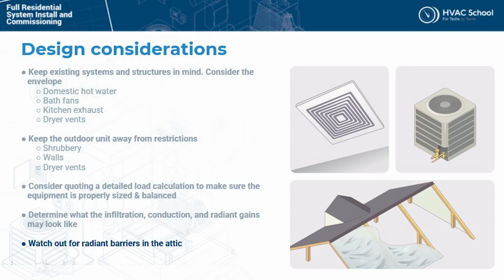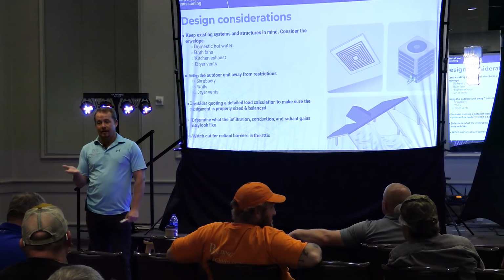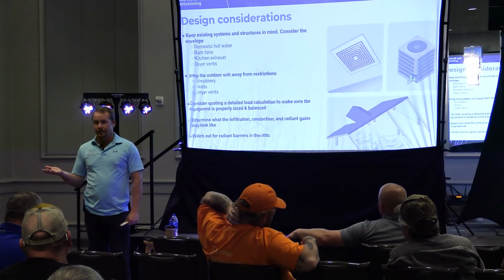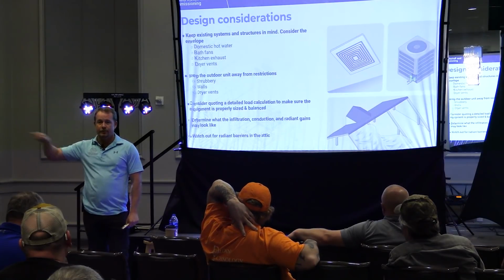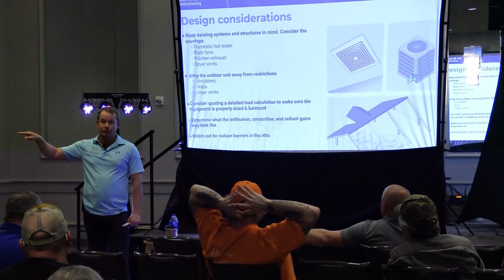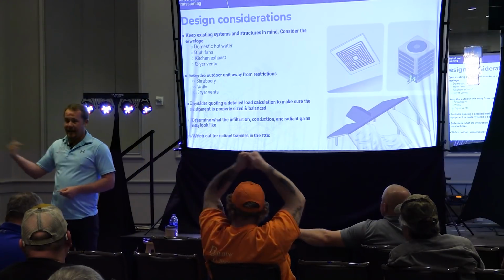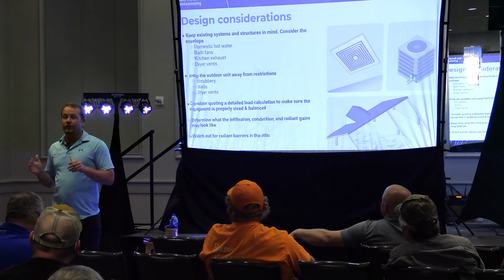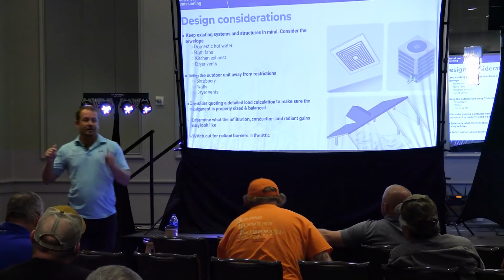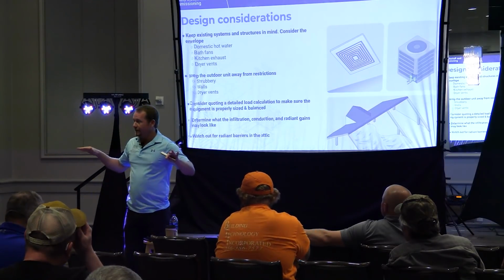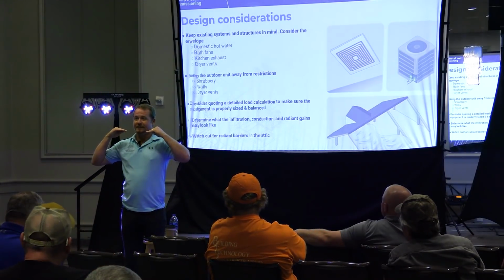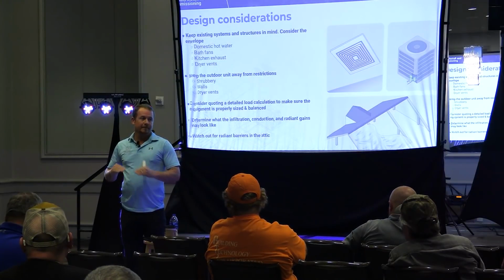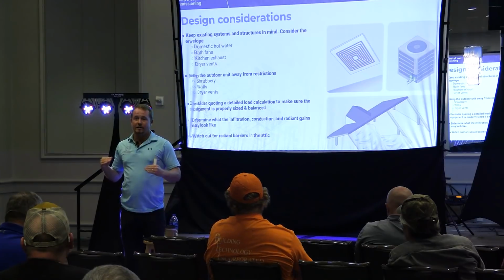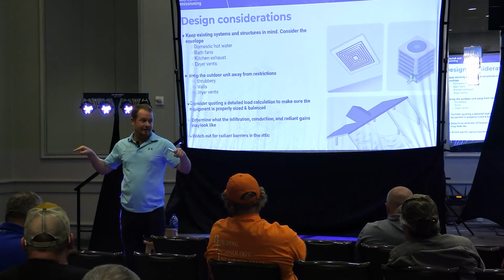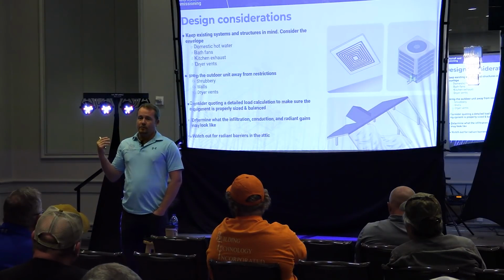Watch out for uncontrolled attics altogether. Because one nice thing about ventilation, at the very minimum, even though the attic is still hot, the dew point in the attic tends to stay closer to the outdoor dew point, which sounds bad, but it's really good because attics can get really bad. Ventilating attics for humidity is pretty good, so long as you're not causing an air exchange to the space. Case in point, make sure that your attic, if it's unconditioned, is sealed as well as possible to the space, full stop. If you want to really solve the problem, then completely seal the attic and put a dehumidifier up there.